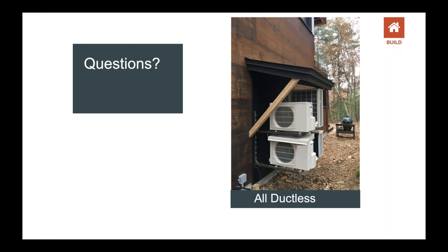This is the last slide in this group, but what I want to point out on this one is really that not only does it have a roof over the top to protect it from rain and snow and icicles that would come down, and elevate it up off of the ground so that you don't have any ice buildup or snow drifts coming up underneath it, but you'll notice that the lower units have a little cap on their roof to actually protect them from the defrost that would pour down from the top unit when it goes into a defrost cycle. During a snow squall or even freezing rain, the units will accumulate some amount of ice on the outdoor unit, and it goes into a short defrost cycle to reverse the cycle of heat and just warm up the outdoor coil to melt off any of the ice and snow, and that'll drip down underneath it. And in this case, the top unit's defrost will drip onto that little roof and pour away harmlessly to the side, and it won't impact the lower unit.